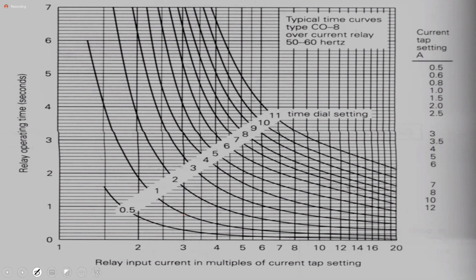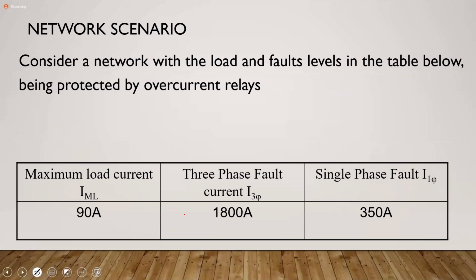So I've just given you some values there, but I want to run through an exercise with you. We are now 15 minutes in. Wow. All right. Let's run through the exercise. So here we have a network, and we are using an overcurrent relay. What you have there are the maximum load current, the maximum fault current, and the minimum fault current. And these are values that we will use to set our relays.